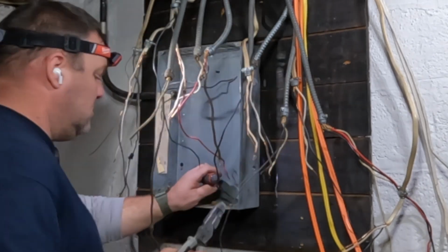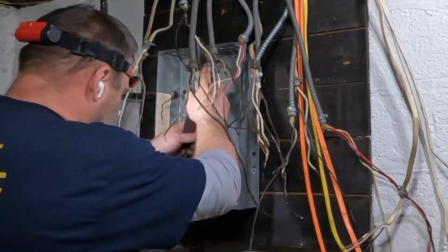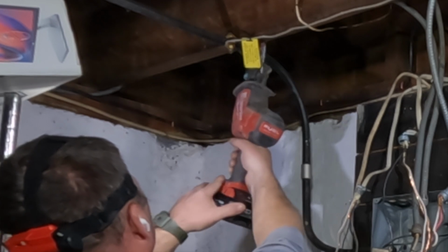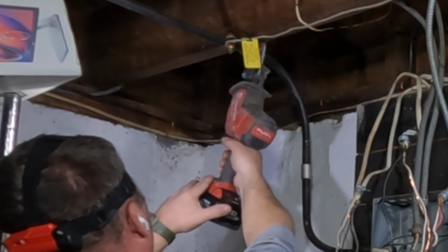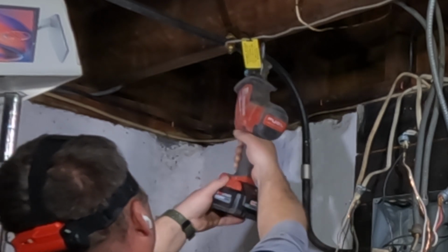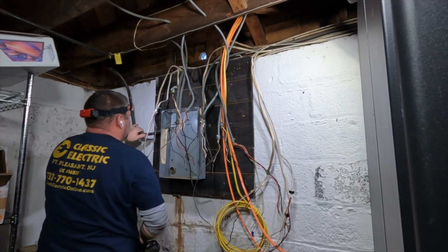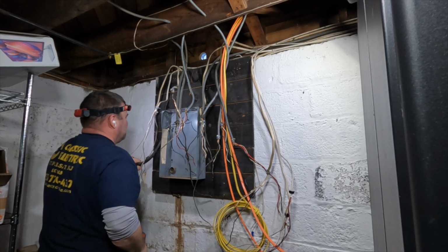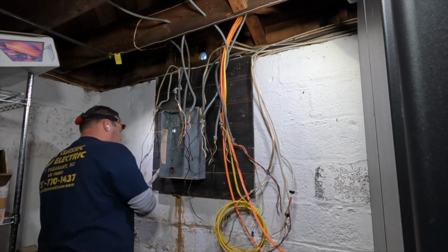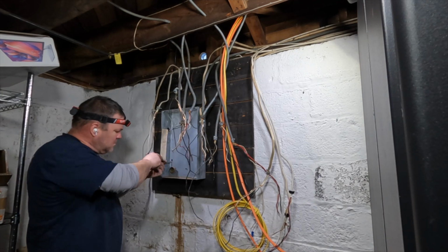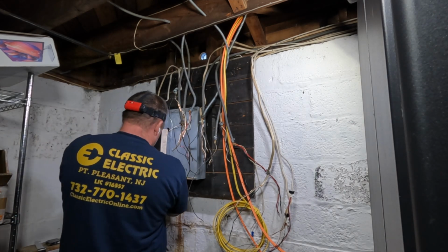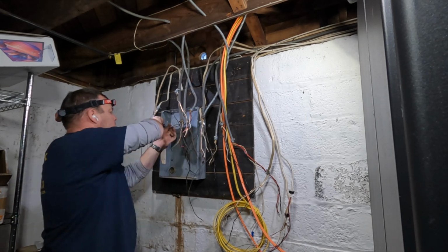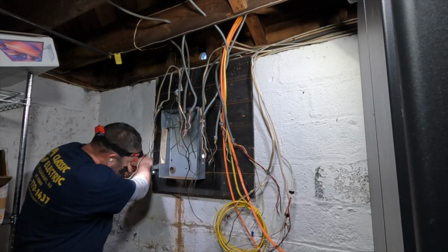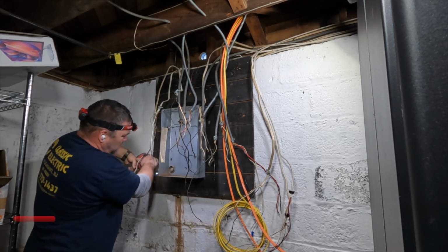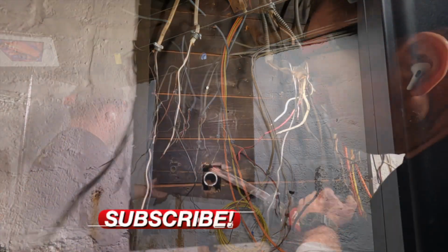I'm also going to be adjusting the length of the BX cable, so I'll have to use my BX cutters to strip it back. This was the old grounding electrode conductor that was sleeved through this rigid metallic conduit that goes from here all the way back to the water main, which is on the other side of the basement. I've never seen protection quite like that before. It's a good thing, I guess, but totally not necessary by today's standards, so to speak.